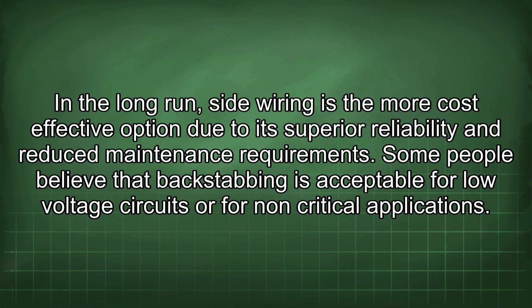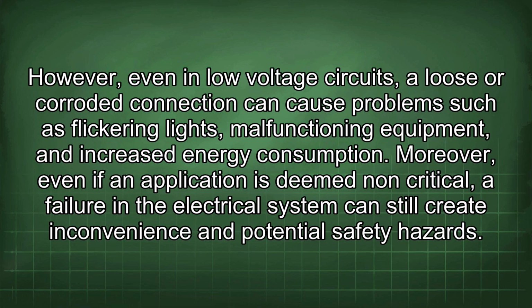Some people believe that backstabbing is acceptable for low-voltage circuits or for non-critical applications. However, even in low-voltage circuits, a loose or corroded connection can cause problems such as flickering lights, malfunctioning equipment, and increased energy consumption. Moreover, even if an application is deemed non-critical, a failure in the electrical system can still create inconvenience and potential safety hazards.